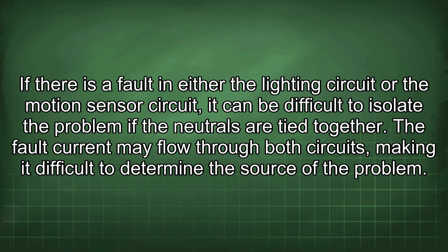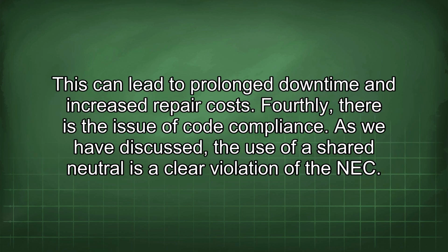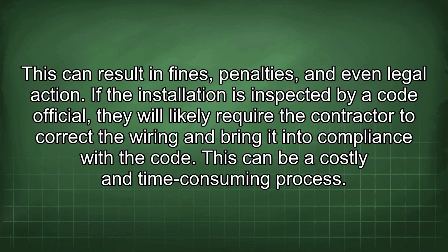If there is a fault in either the lighting circuit or the motion sensor circuit, it can be difficult to isolate the problem if the neutrals are tied together. The fault current may flow through both circuits, making it difficult to determine the source of the problem. This can lead to prolonged downtime and increased repair costs. Fourthly, there is the issue of code compliance. As we have discussed, the use of a shared neutral is a clear violation of the NEC. This can result in fines, penalties, and even legal action.